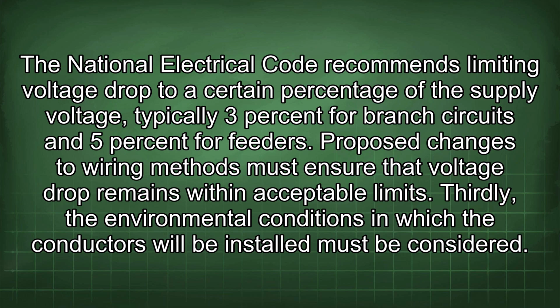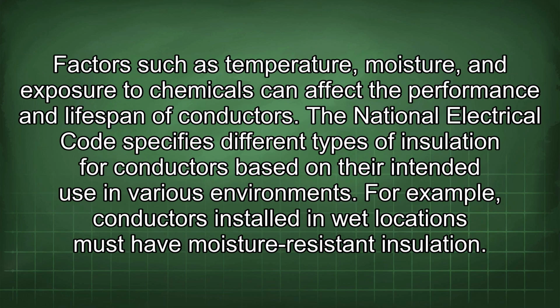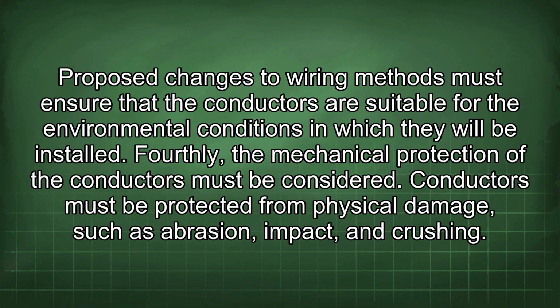Thirdly, the environmental conditions in which the conductors will be installed must be considered. Factors such as temperature, moisture, and exposure to chemicals can affect the performance and lifespan of conductors. The National Electrical Code specifies different types of insulation for conductors based on their intended use in various environments. For example, conductors installed in wet locations must have moisture-resistant insulation. Proposed changes to wiring methods must ensure that the conductors are suitable for the environmental conditions in which they will be installed.